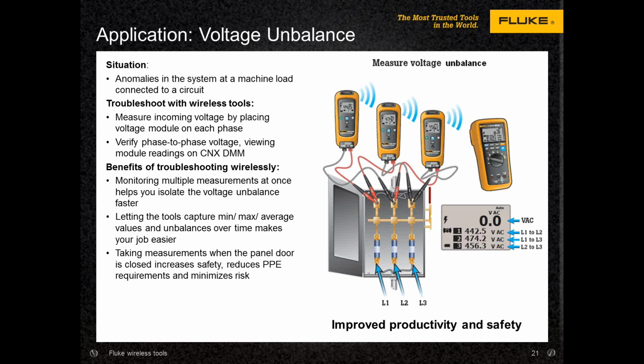You'll be able to see the readings very quickly. In the life of an electrical system, voltage unbalance typically doesn't have as much leeway as current unbalance. There are rough standards for voltage unbalance. You want it 2% or less in most cases, so you want those three readings to be an average of 2% or less within each other, so you don't have any issues there. In current, typically I'll throw a number out there, and it's generally 8% or less in most cases. Otherwise, if you have more than an 8% difference, you probably have some power quality issues you need to look for, or some other circuit systems you need to look at.